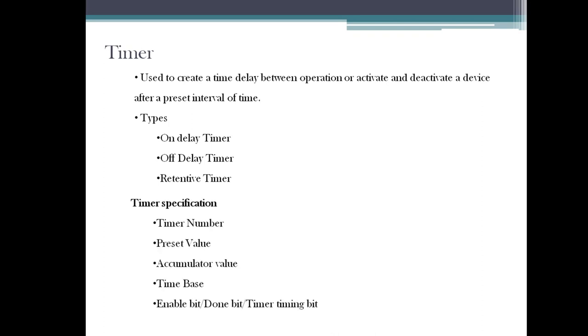The first one is timer number. Timer number is nothing but a timer address. If we need three to four timers in our project, how are we going to differentiate them? By using the timer number. You can start from zero and up to 256. You can use maximum 256 timers in a project, starting from T4:0 to T4:255 in Allen Bradley.